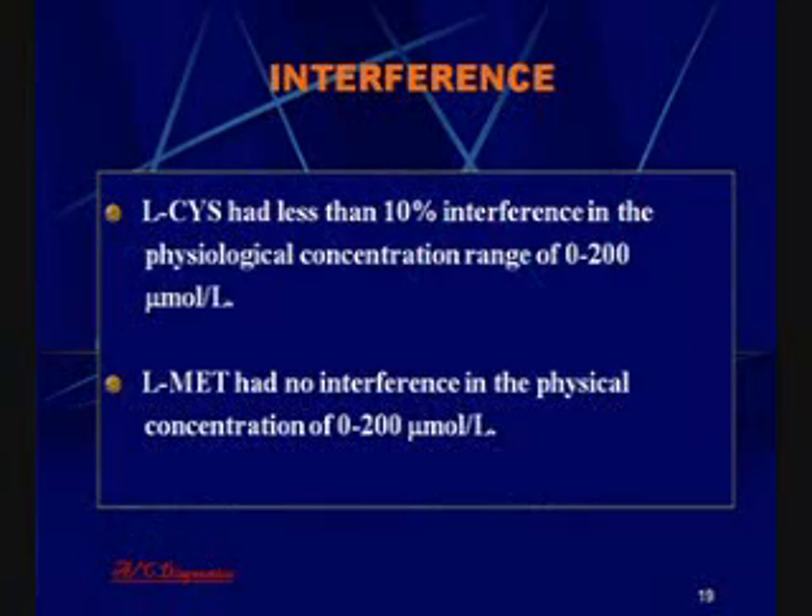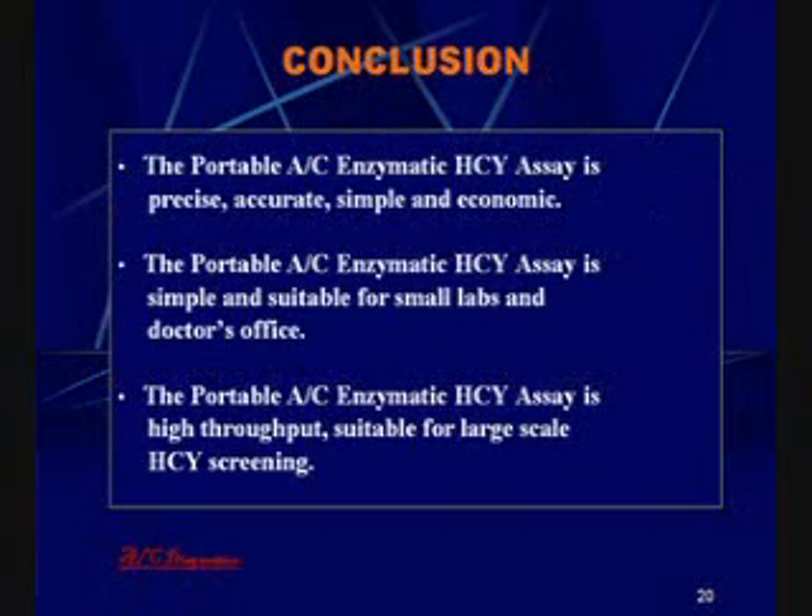The enzymatic homocysteine assay on the portable fluorescence reader had an interference of cysteine of less than 10%. L-methionine had no interference in the assay. In conclusion, the homocysteine assay performed on the portable fluorescence reader is precise, accurate, simple, and economic. This assay is very suitable for small laboratories and the doctor's office, allowing the assay to be made available to a very wide population base.